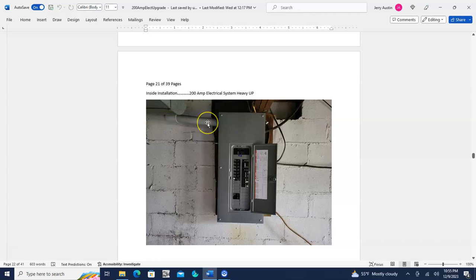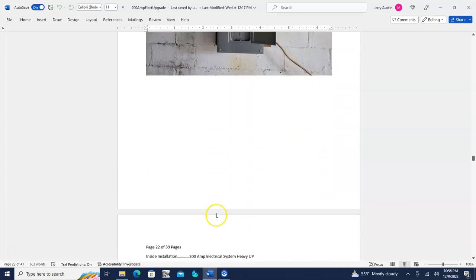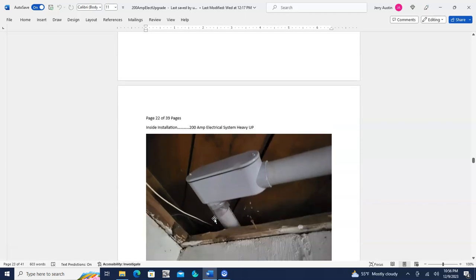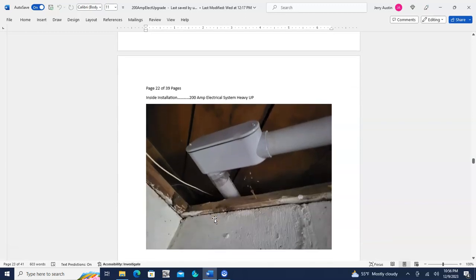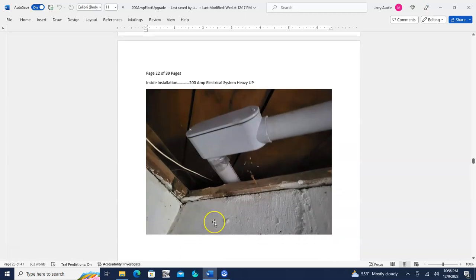There's 3 of them. There's 2 electric power leads, and then you've got the ground power lead coming into the box. This is right here, comes off down here. This is for the dryer, and there's another wire coming off up there, and most of the wires hook in through the top. What we did is we just took the old wires in the old box out and put the new box right in the same place, a new circuit breaker box right in the same place.